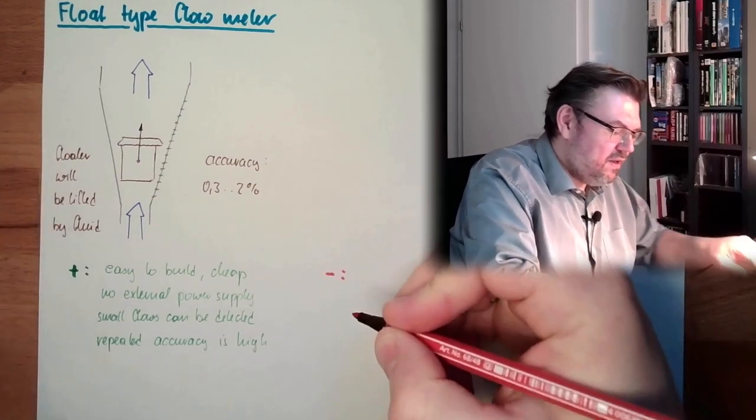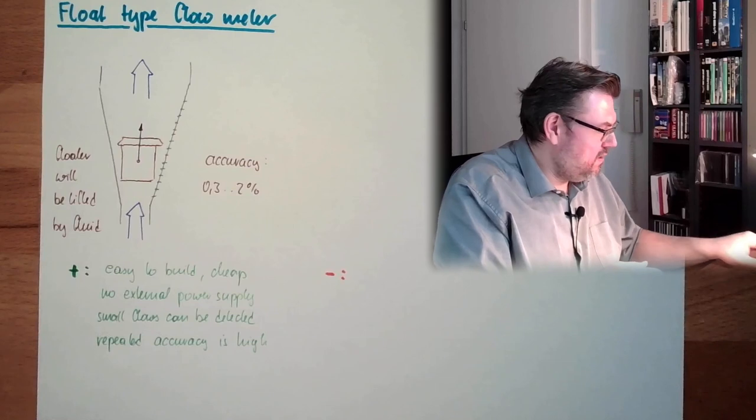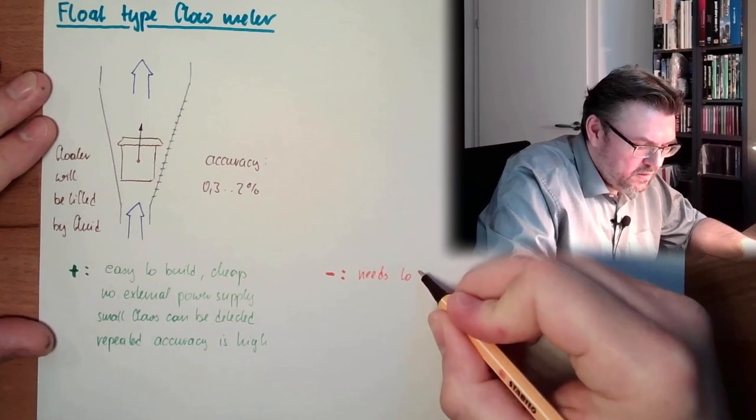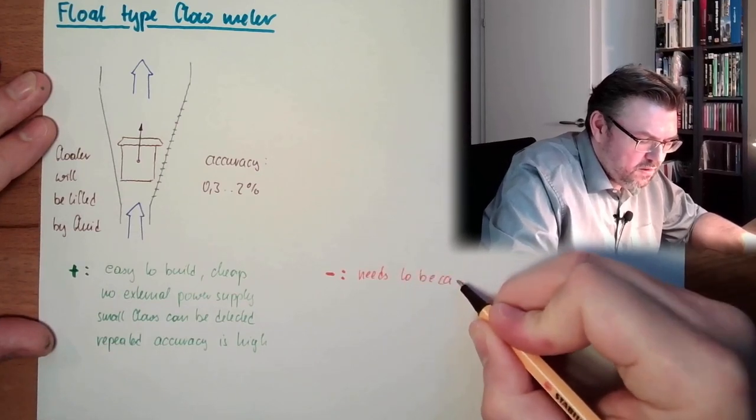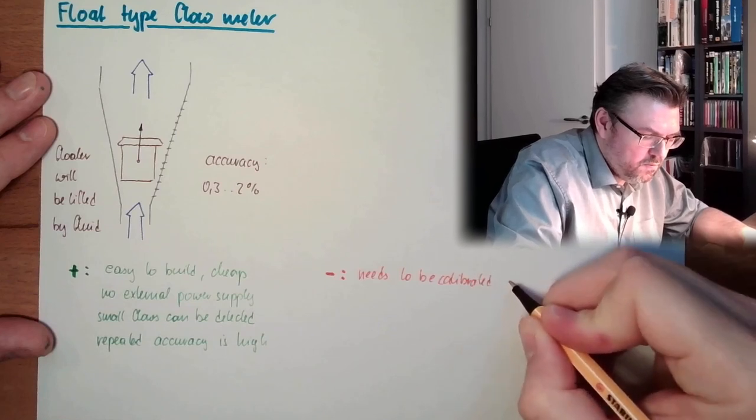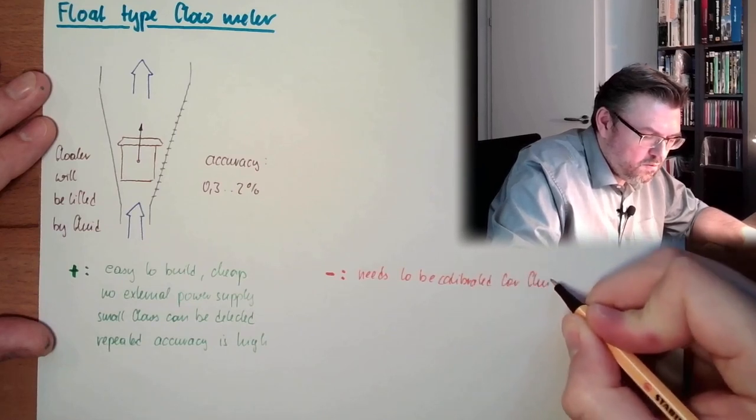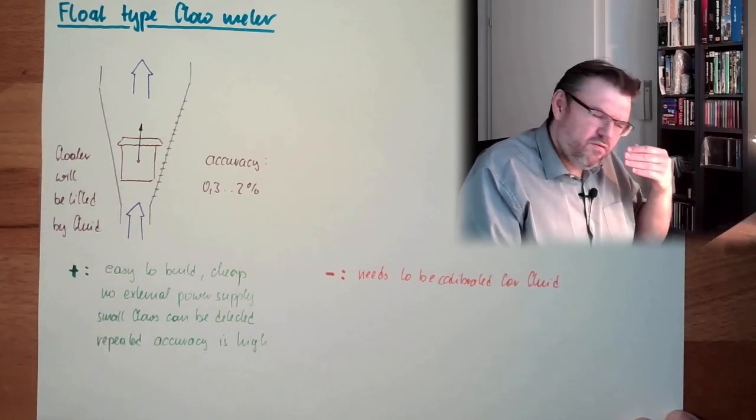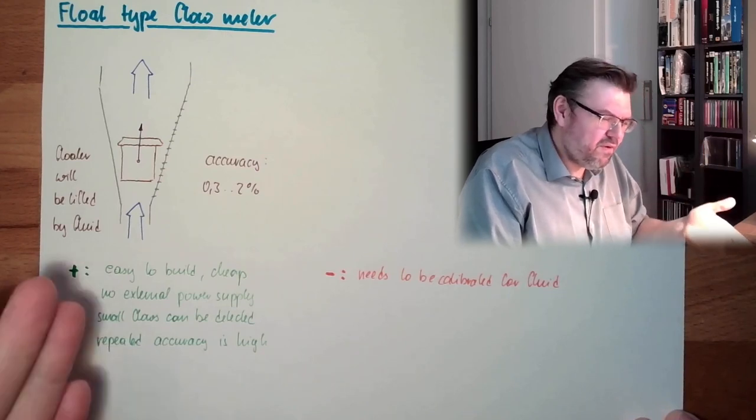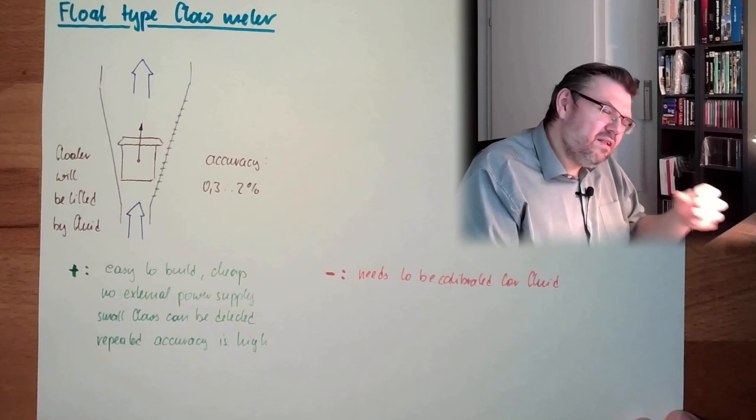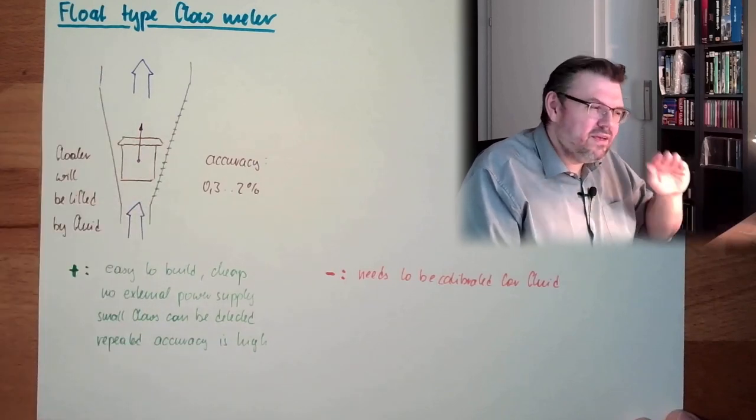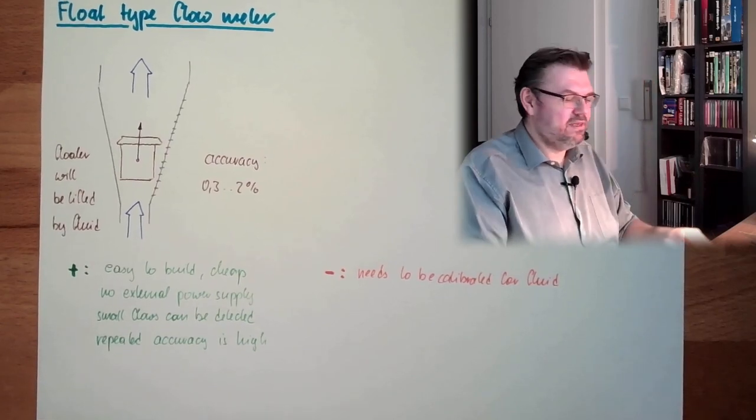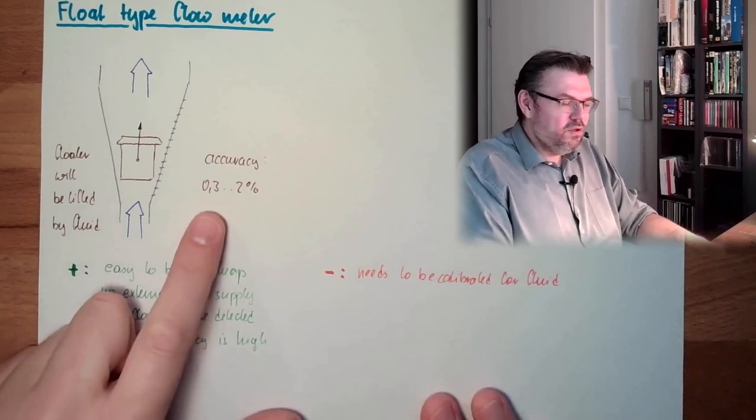It needs to be calibrated for the fluid, needs to be calibrated for a certain type of fluid. If the fluid has a different property, like a different pressure, a different density, or something like this, we have to adapt the scale. We have to calculate from the scale to another scale. So we have to scale the scale. This needs to be calibrated. Then the total accuracy is fine.